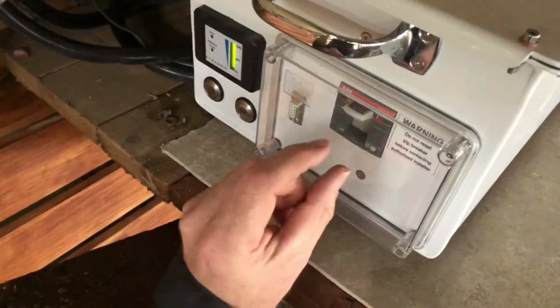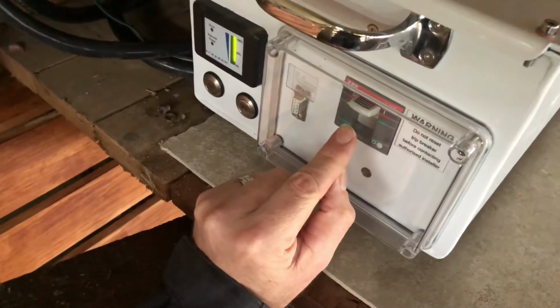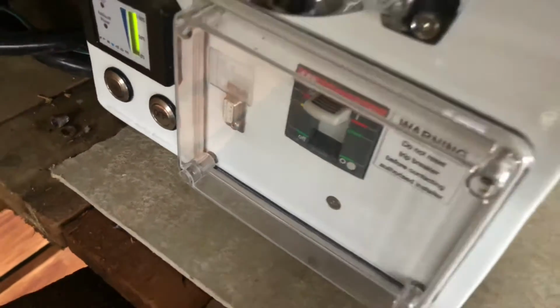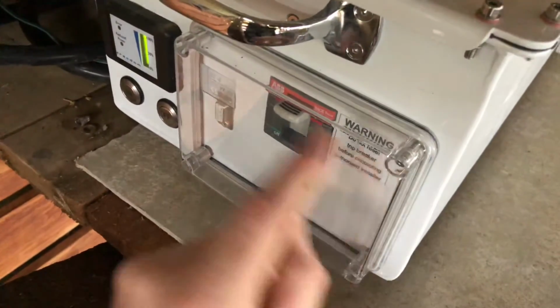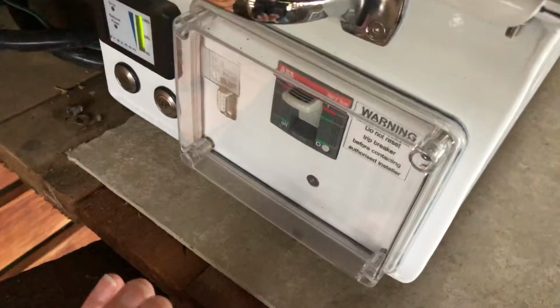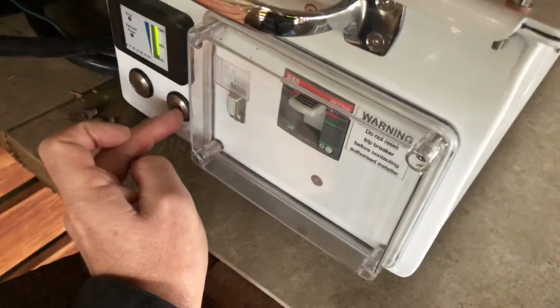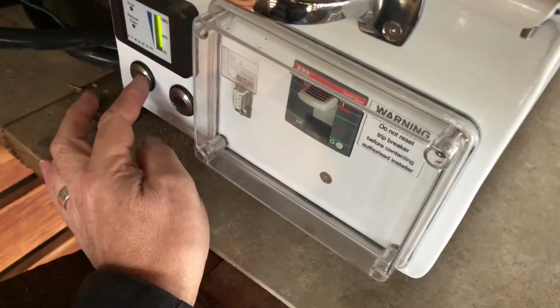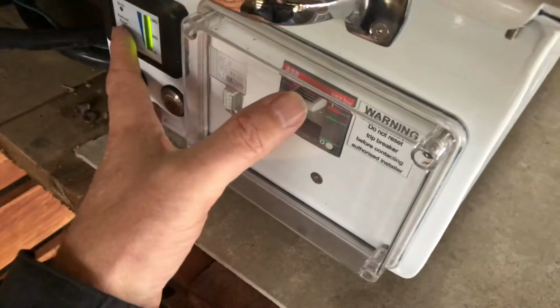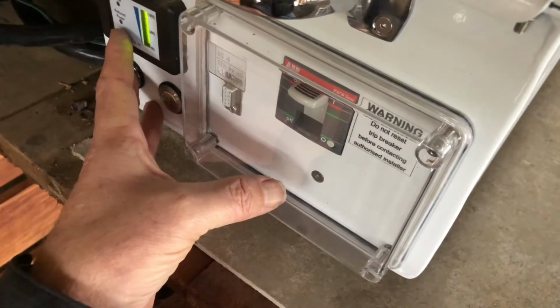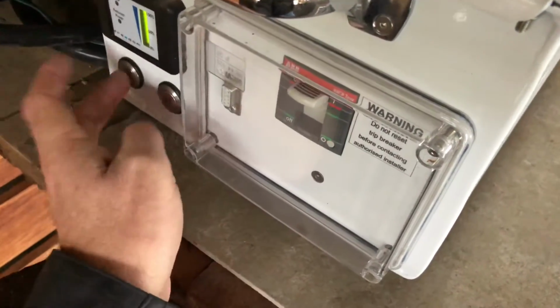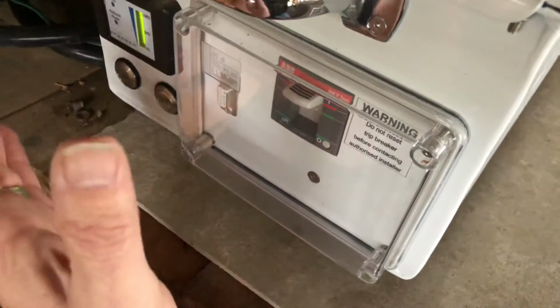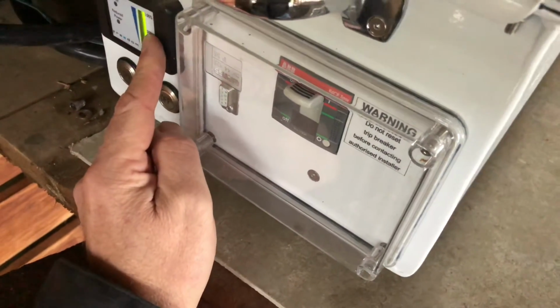Now the breaker will trip only a little bit, just down to the yellow line. The breaker then needs to be reset. The method for resetting is to undo the 4 screws, take the cover off, press the off button, then press and hold the on button, push the breaker right to the bottom, and then push the breaker right up while you're holding the on button. That will then bring power back onto the system.